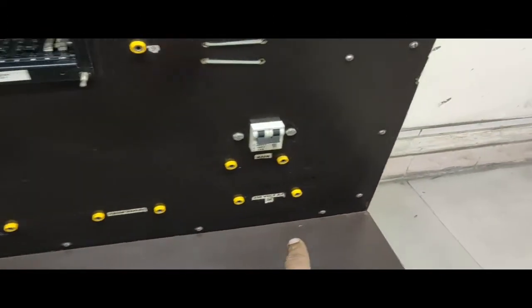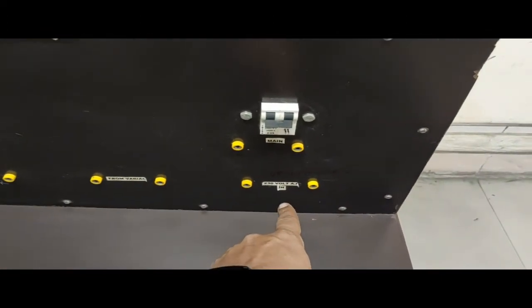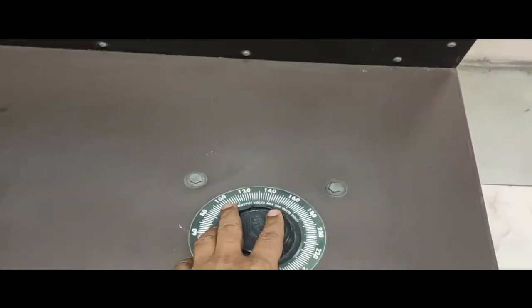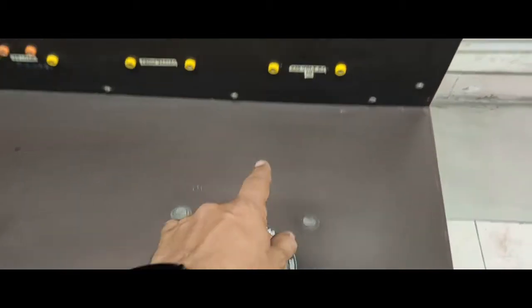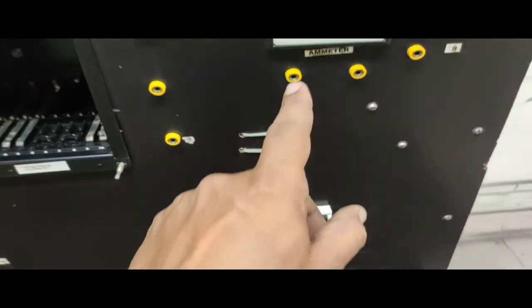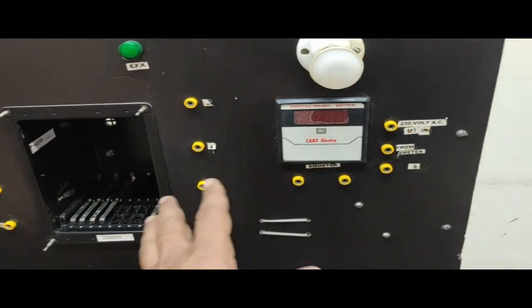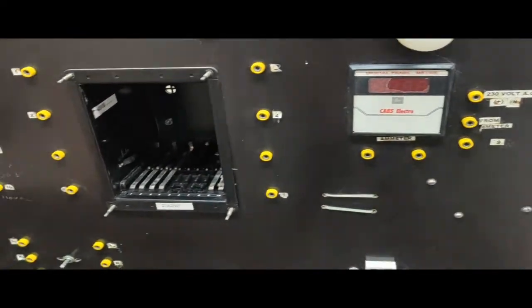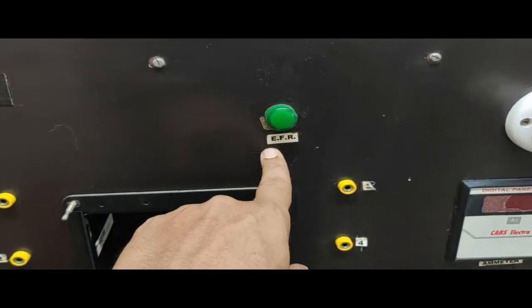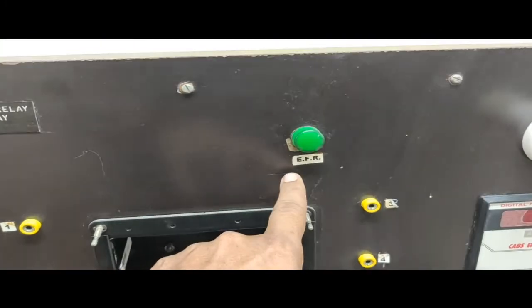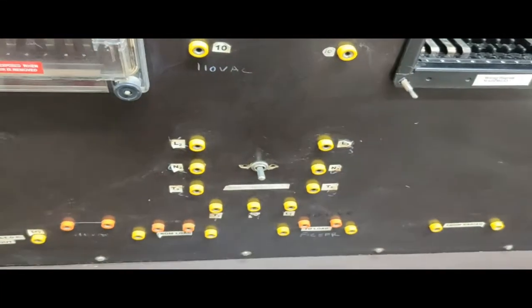Now coming to this, this is the 230 volt AC in. So one variac is there for variable voltage. MCBs are there. This is one ammeter which can measure the current flowing to the relay coil. Now these are the earth fault relay indicators. It indicates that when the earth fault relay is connected, this light will glow. Now this is one switch.